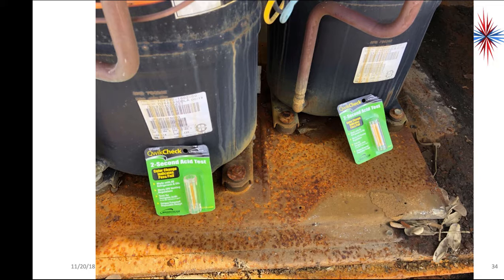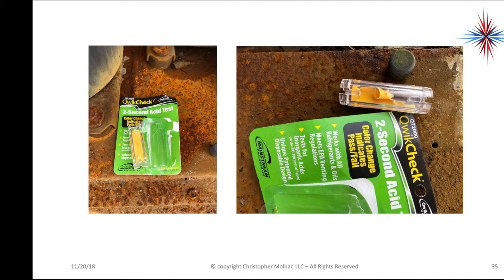So while I'm in the compressor cabinet, I decided that since we're looking for an electrical failure, I wanted to do a quick acid check. Okay, I used the QwikChecks. Basically what it is, it's a little cylinder with some reactive paper inside. You blow refrigerant through it, okay, and it actually turns pink if there's acid in the refrigeration oil. So once again, did both of them. Both came back negative on acid.